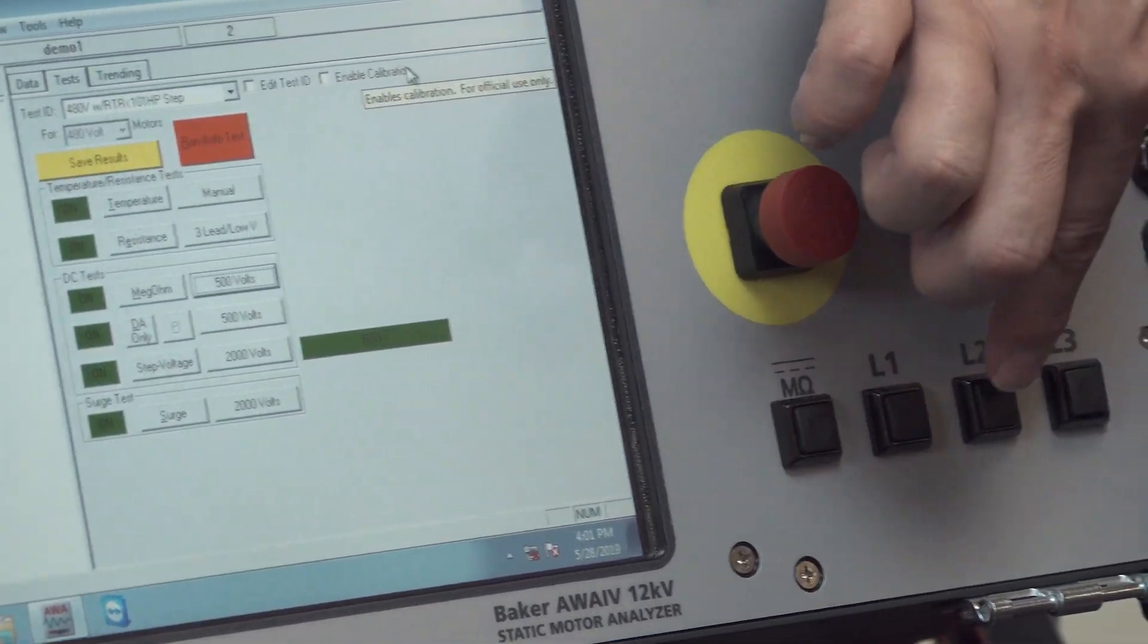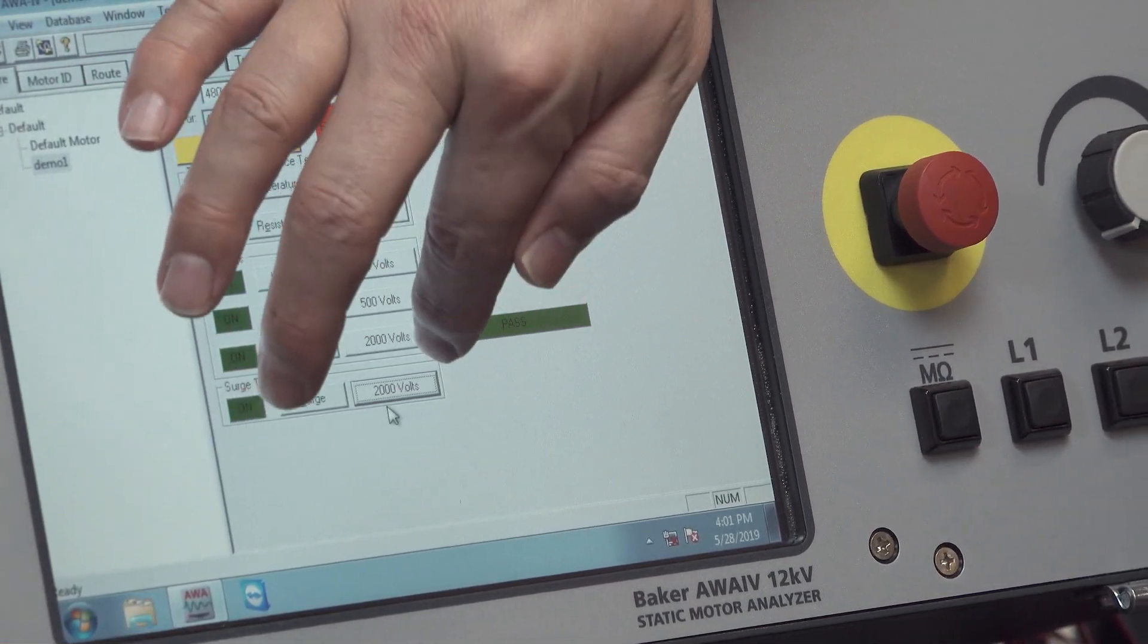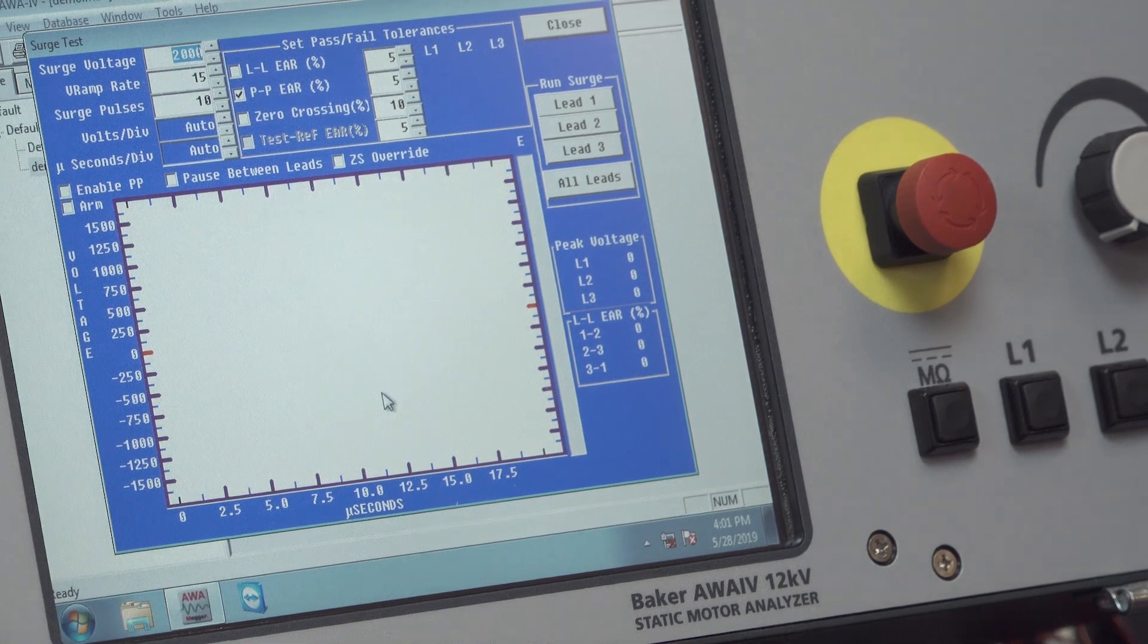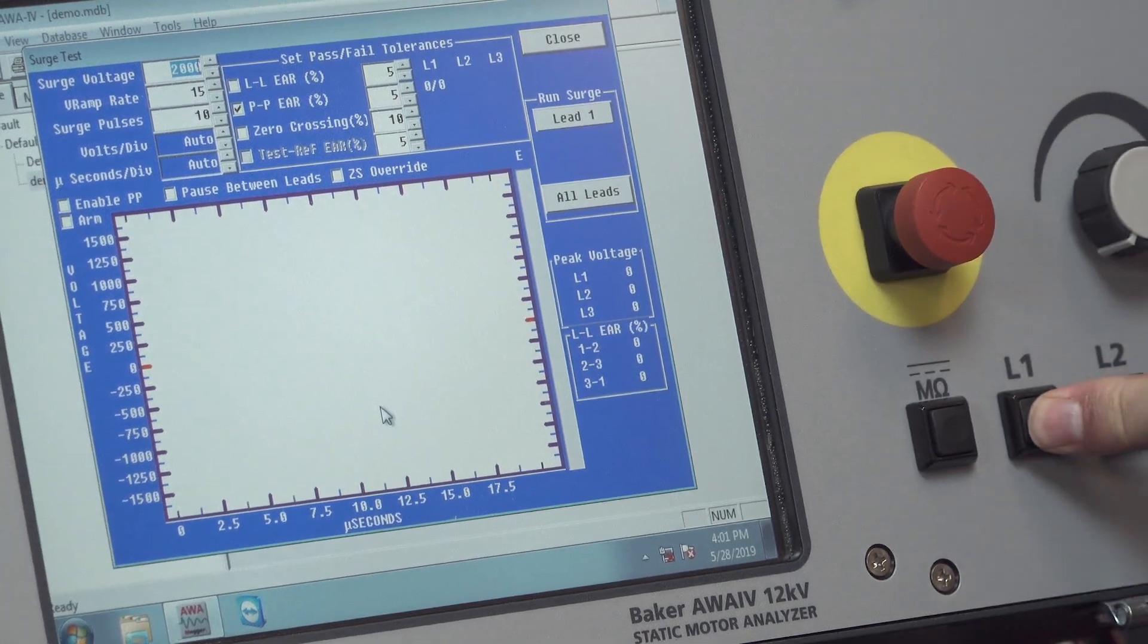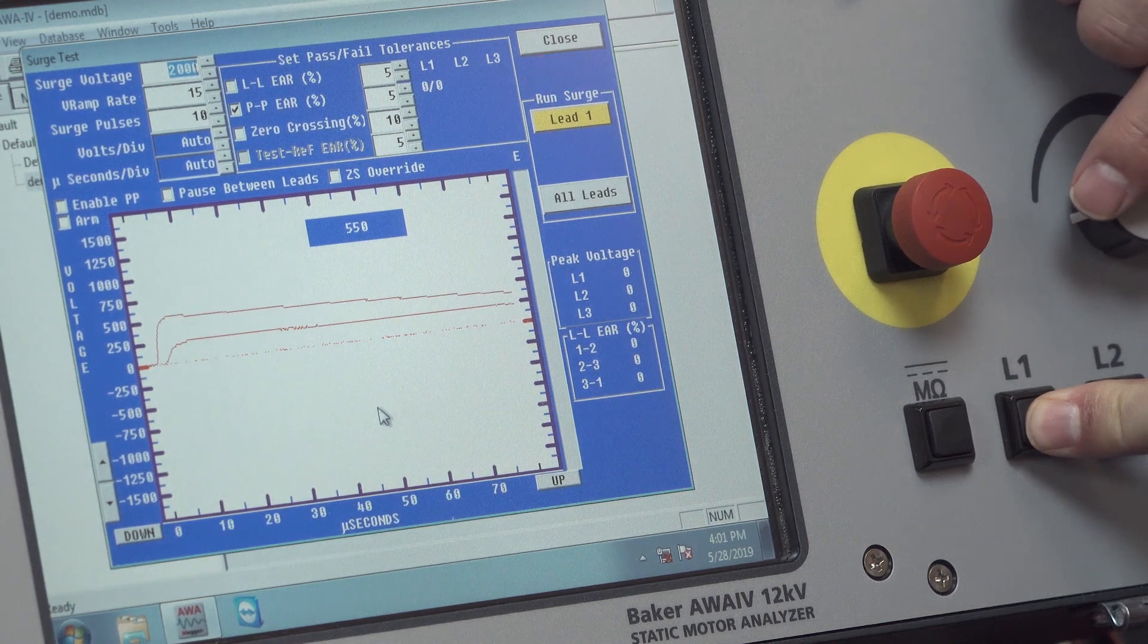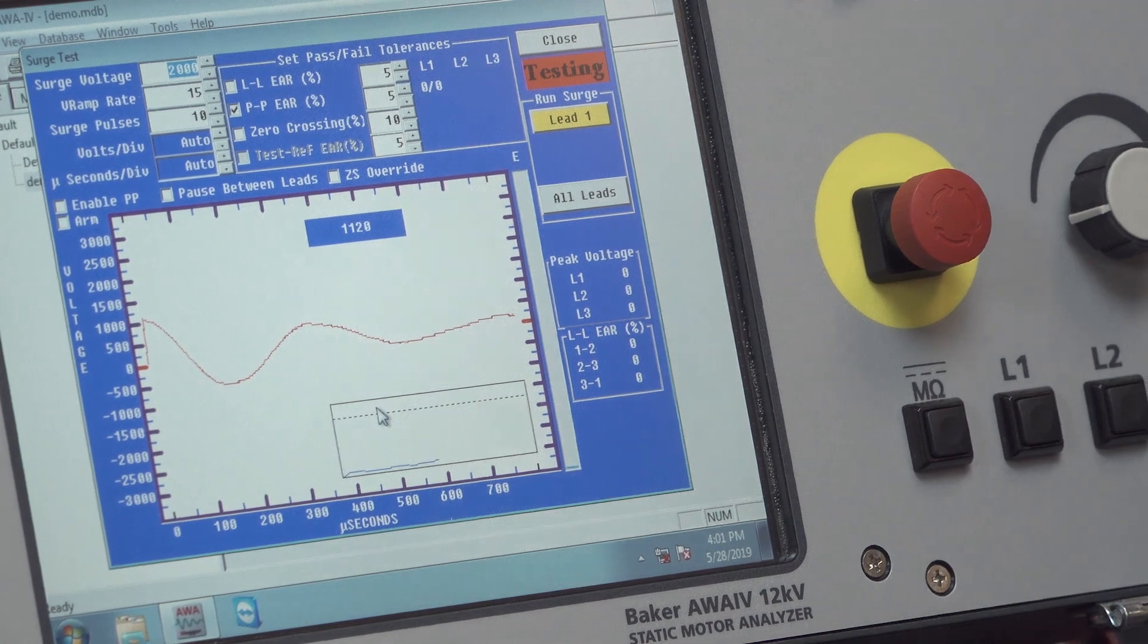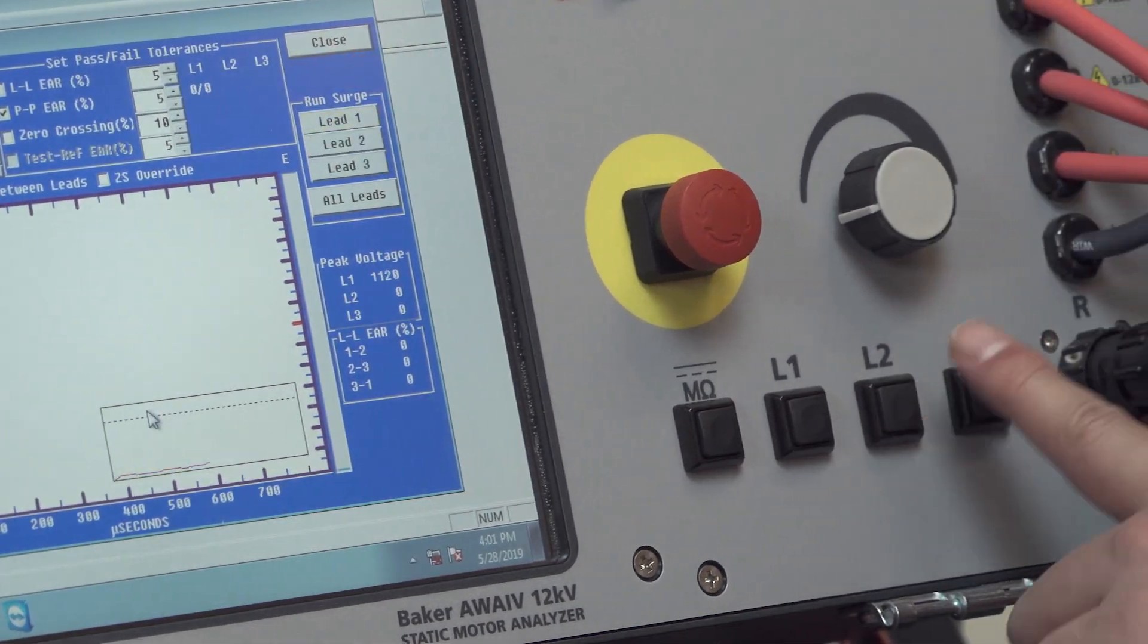The L1, L2, L3 are used similarly, but for surge testing in a manual mode. Pressing L1 will energize lead one, and then you would control the voltage with the potentiometer as you would for manual testing. Test to lead two, test to lead three.